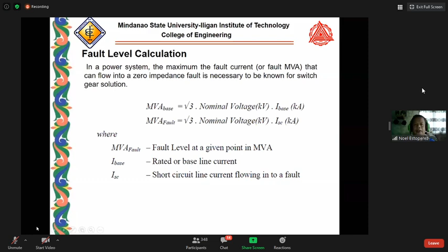In a power system, the maximum fault current that can flow into a zero impedance fault is necessary to be known for switchgear selection. So, the MVA fault here is the fault level at a given point in MVA. If I base is the rated or the baseline current, and the short circuit line current is flowing on the fault, we want to solve for the fault MVA. So this is now the fault level, the ratio of the short circuit MVA over the base.